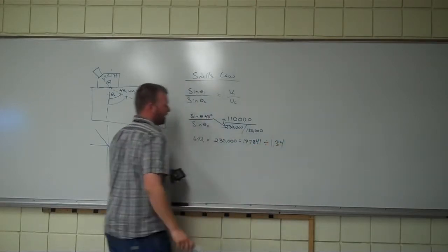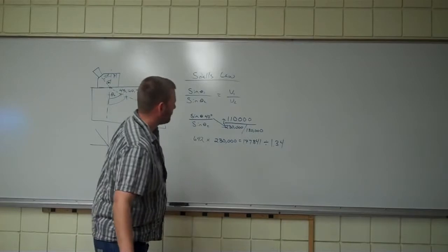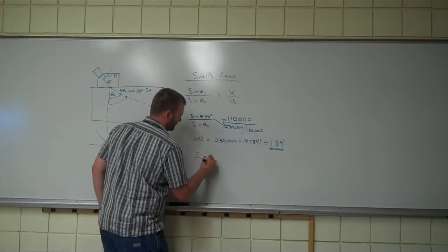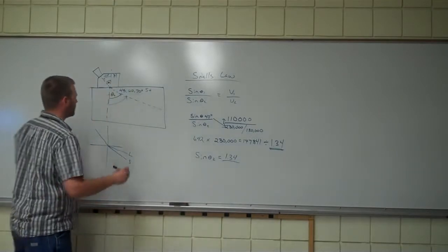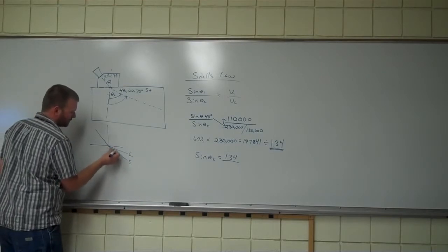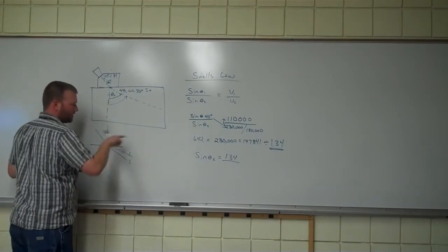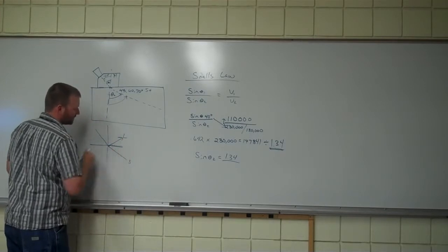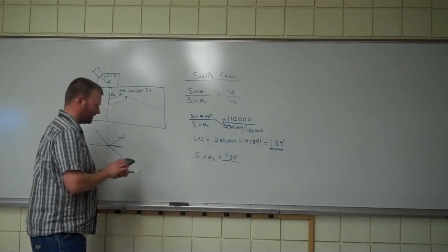of 1.34, which in turn, if we do inverse sine of that, tells us that we have an error. If you have anything greater than 1 when you get to the sine, this means that you've passed either the first or second critical angle. So that means this: an incident wave comes in, again a longitudinal wave coming up. We keep bending this thing down far enough, and we're going to have a longitudinal wave that's either scooting along the surface or has been completely bounced out, leaving us with just a shear wave. In this case, that's what's happening, and that's not a bad thing.